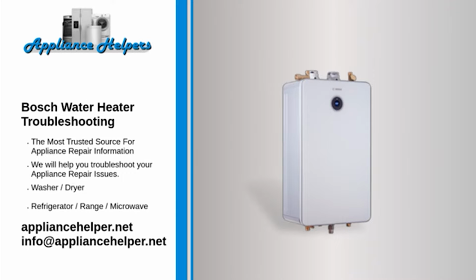There is low water flow or pressure. There might be too many hot water applications used altogether. Or, there is too much flow being demanded. Your heater can support two 2.0-2.5 GPM shower heads simultaneously or multiple sink applications. A greater draw leads water pressure to drop and flow in the taps will be reduced as well. Make sure that gas pressure follows the specifications listed in the manual. You may need a gas pressure reading for this and you need a gas technician to do this.